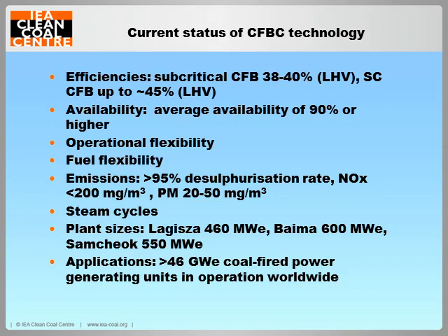A modern CFBC plant can achieve an in-bed sulfur removal efficiency of 95%, and the emissions of NOx and particulates are less than 200 and 50 milligrams per cubic meter, respectively. Recent CFBC units have used post-combustion controls such as dry scrubbers or SNCR to further reduce emissions of SO2 and NOx to meet increasingly stringent emission requirements.